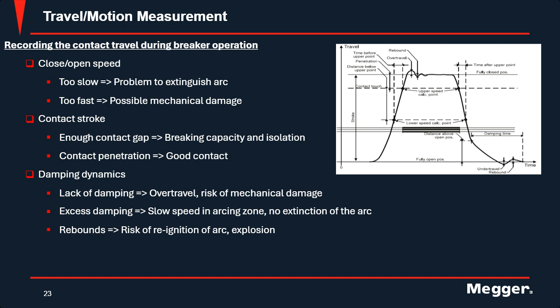And then obviously rebound is one of the most serious of the problems you can have. There's a risk that you reignite that arc by the contacts coming back close enough to bridge that gap, and the arc comes back on. In extreme circumstances, that can lead to the breaker exploding. So travel and motion measurements are very good. Most people, from my experience, especially customers, just want to see the timing analysis. I do have a case study we're going to look over in just a little bit that points out the reason why doing the motion or the travel analysis is a very big benefit and should be done when you're doing timing.